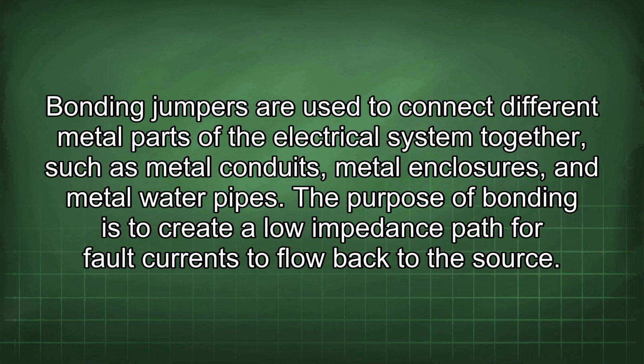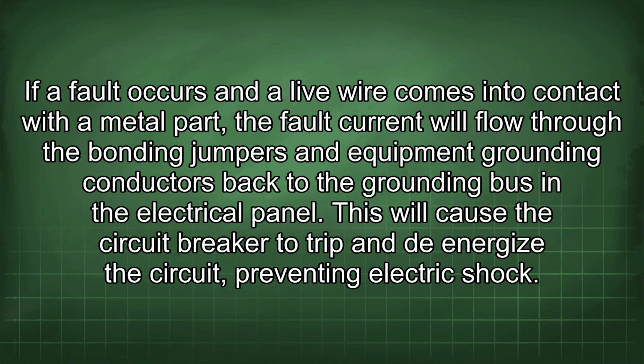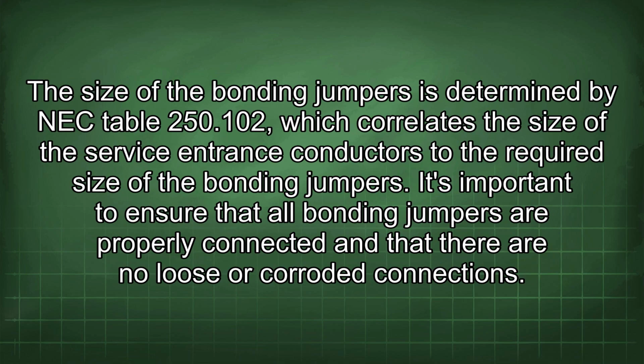back to the source. If a fault occurs and a live wire comes into contact with a metal part, the fault current will flow through the bonding jumpers and equipment grounding conductors back to the grounding bus in the electrical panel. This will cause the circuit breaker to trip and de-energize the circuit, preventing electric shock. The size of the bonding jumpers is determined by NEC Table 250.102, which correlates the size of the service entrance conductors to the required size of the bonding jumpers. It's important to ensure that all bonding jumpers are properly connected and that there are no loose or corroded connections.